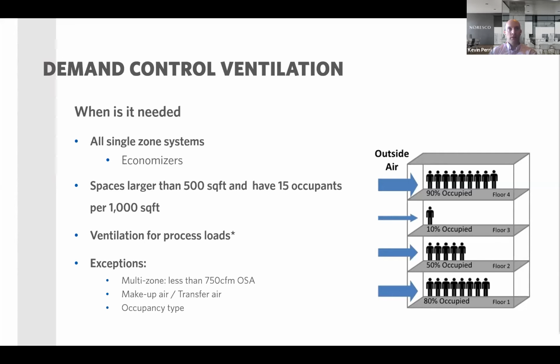Also, any spaces larger than 500 square feet that have occupants on average of 15 occupants per 1,000 square feet would require demand control ventilation. So that's not new. What's new on that part is the occupants. It used to be on average 25 occupants per 1,000 square feet. They've reduced that to 15 occupants per 1,000 square feet. So when you're designing things, that number is going to be a new number to follow.